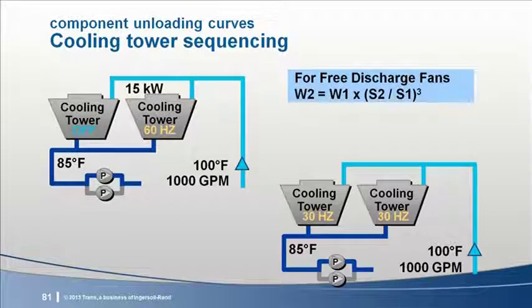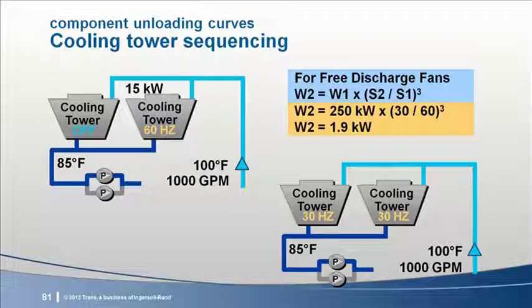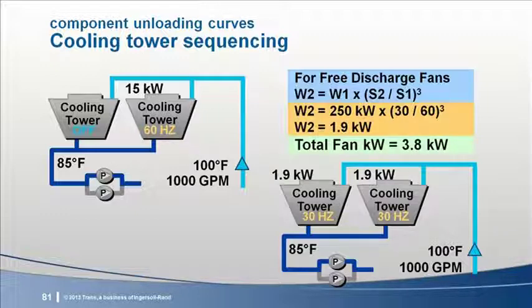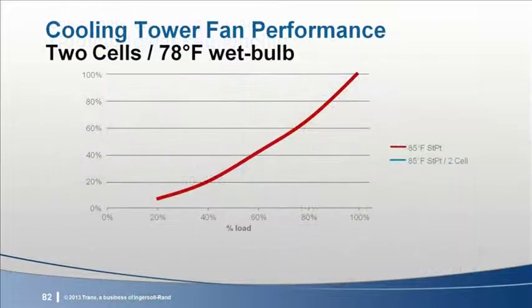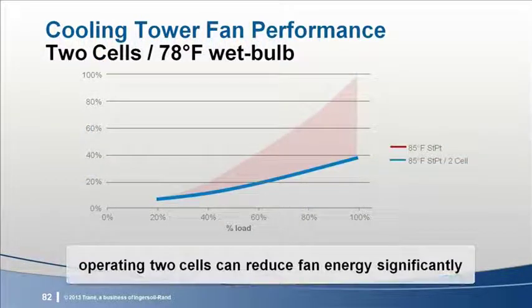What would be the power draw of two free discharge cooling tower fans meeting the same conditions as one? If we assume the ideal case and assume energy savings to the cube of the load, we would see that the power draw of each fan would be approximately 1.9 kW. That makes the power draw of both fans together 3.8 kW. That's a fan energy savings of over 70% with no negative impact on the performance of any other part of the system. If we plot the one tower and two tower fan performance on the unloading chart, we can see the potential fan power savings at various tower loads.